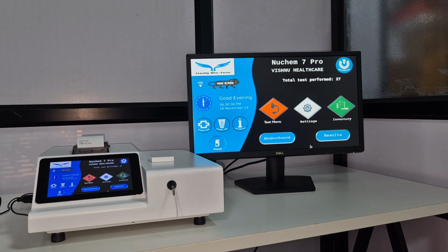This analyzer supports all kinds of chemistries. It supports up to 10 different methods of test. It could be endpoint, based on standard, factor, or multi-standard, supporting up to 10 standards, with single filter and dual filter readings. And it also supports sample blank and sample blank with standard. And fixed time, it supports with factor, with standard and multi-standards up to 10 different standards.